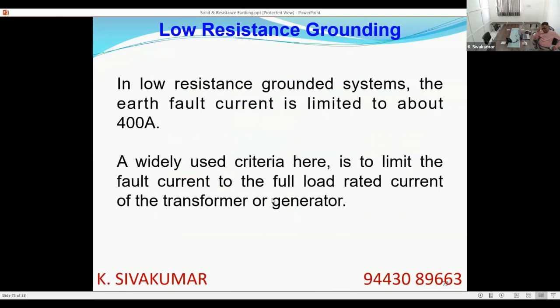Here, generally, what is the criteria? The criteria is to limit the fault current to the full load rated current of the transformer. Why select 400? Why not 200? Why not 1000? The general guideline is to limit the current to the rated full load current of the transformer or generator. Mind you, for a generator, always keep the core damage point in mind. But if you are ready to ignore core damage, or the core damage value is higher, you can also go for the rated full load current of the generator.